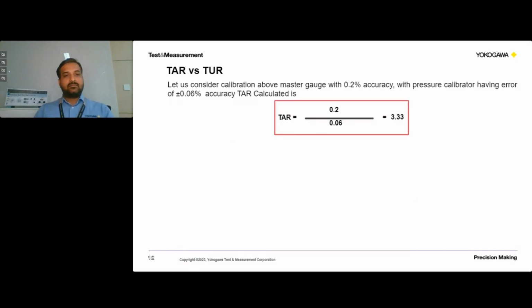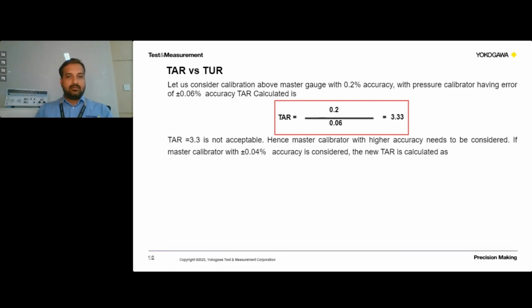Similarly, next we will consider what kind of master gauge or master calibrator we have to choose for the calibration of this 0.2 percentage of accuracy master gauge, which we saw in the previous example. So let us consider a master pressure calibrator having 0.06 percentage of accuracy. So we are calibrating this previous master gauge with this master pressure calibrator having 0.06 percentage. The test accuracy ratio achieved is 3.3. So that means this master pressure calibrator is not meeting the requirement of 1:4 ratio. So we need to consider a better pressure calibrator which is having a better accuracy.